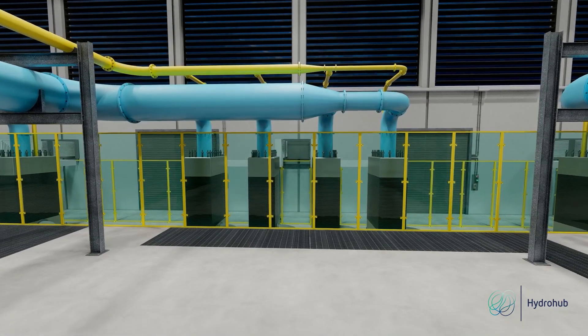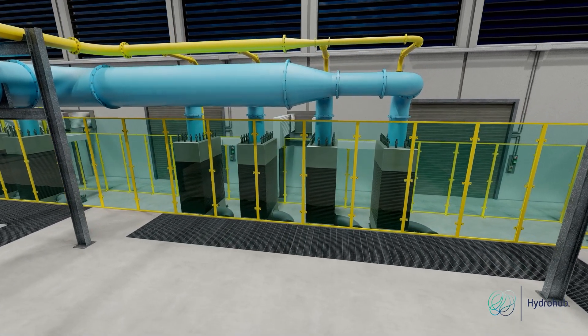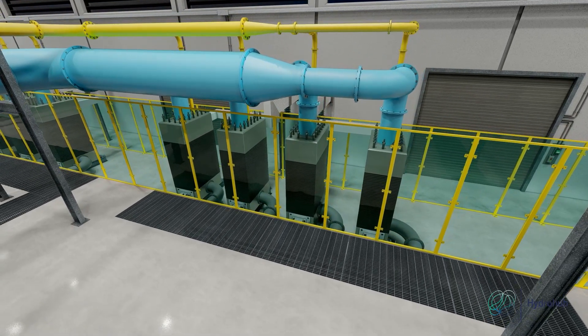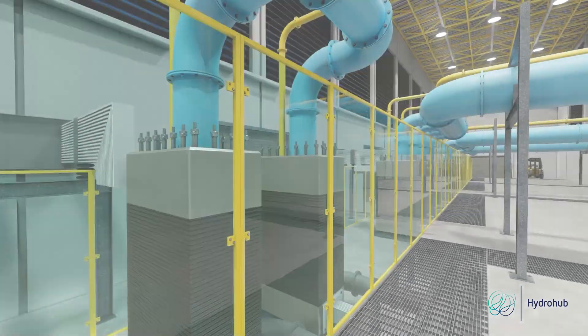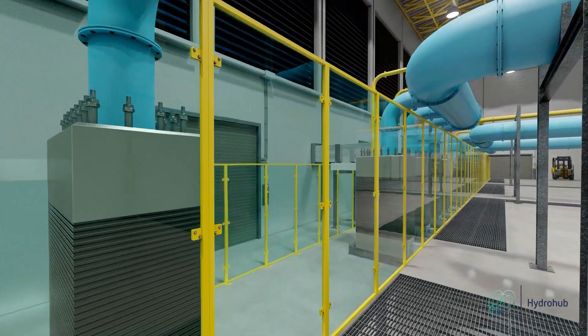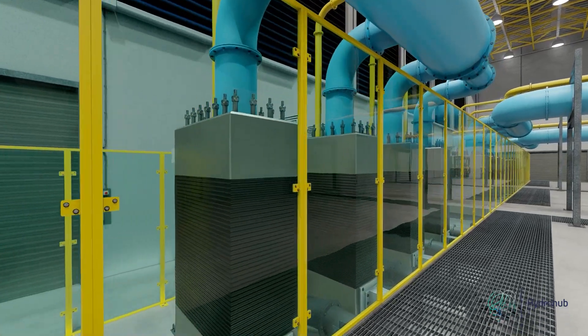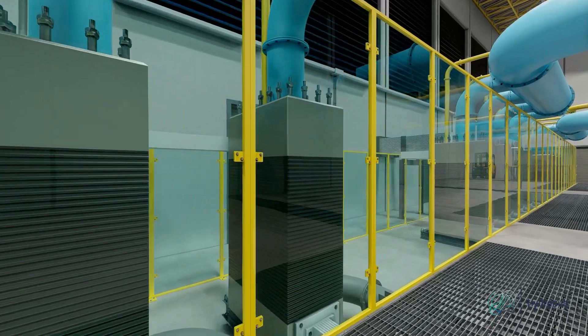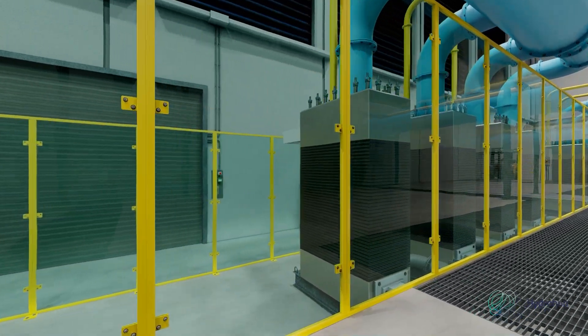To explore the effect of different technologies, a version of the design was also made with 10 megawatt PEM stacks of 310 cells, operating at 70 degrees Celsius. These stacks use high-performance materials, thinner membranes and less scarce materials. The electrode materials contain reduced iridium loading at the anode and have a current density up to 3.5 amps per square centimeter.